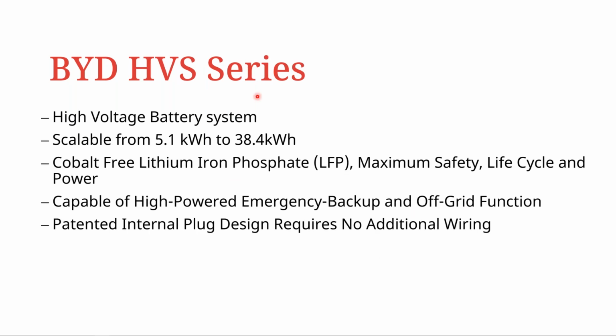With BYD's HVS series, the high voltage battery systems, it is scalable from 5.1 kilowatt hours, or 2 modules, up to 38.4 kilowatt hours available. Again, these are cobalt-free lithium iron phosphate batteries, or LFPs, and they're also capable of high-powered emergency backup and off-grid functionality. They've got a patented internal plug design requiring no additional wiring. They're simply modules that stack on top of each other to allow for an integrated battery backup.